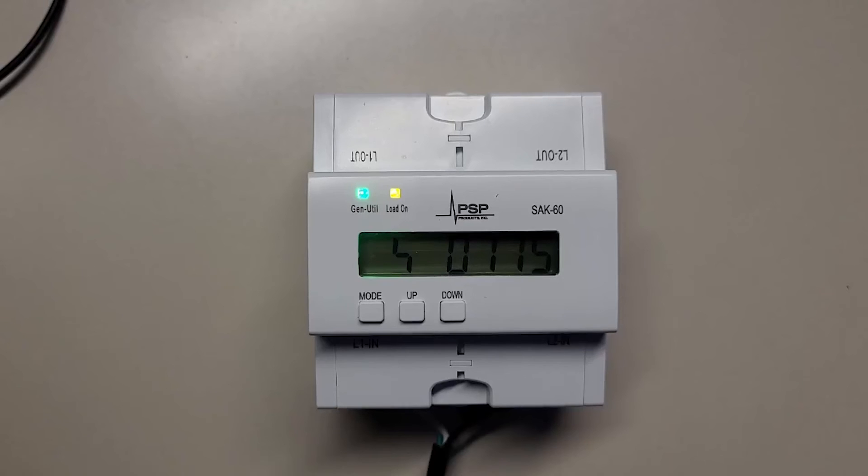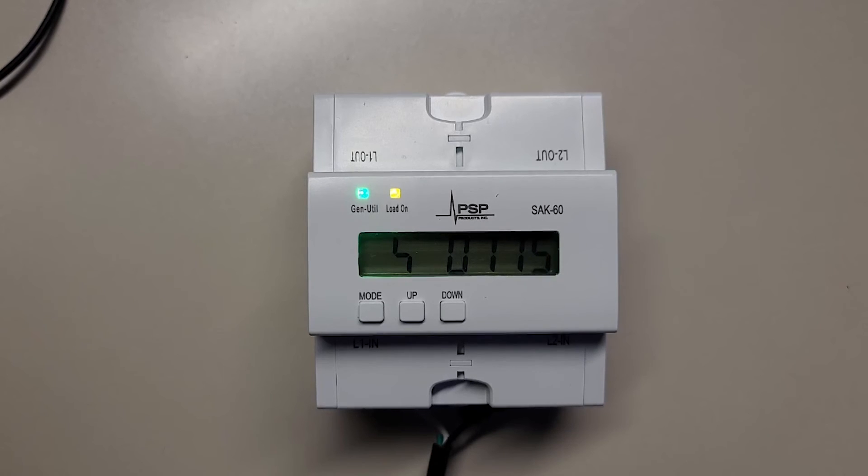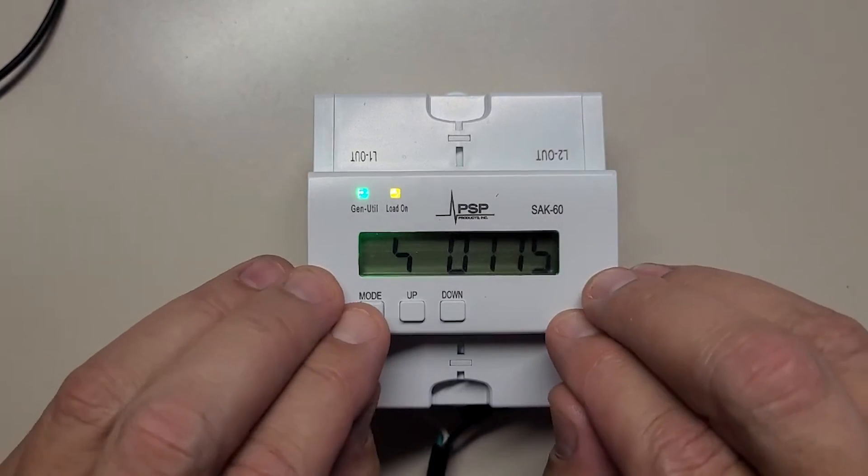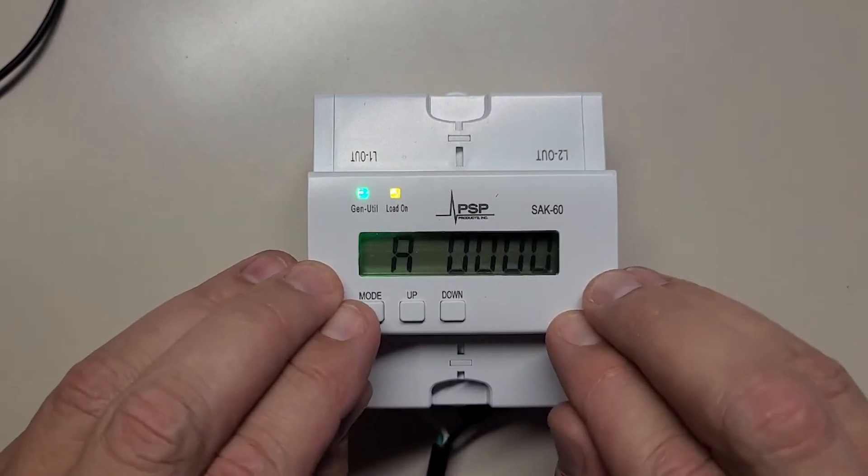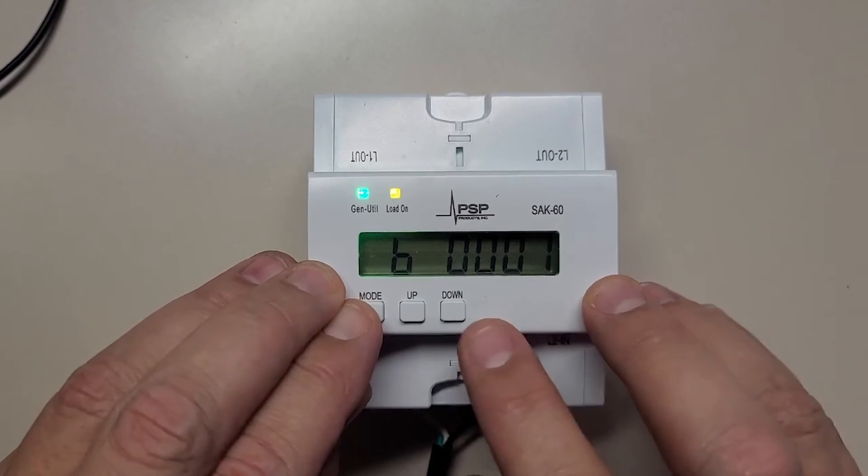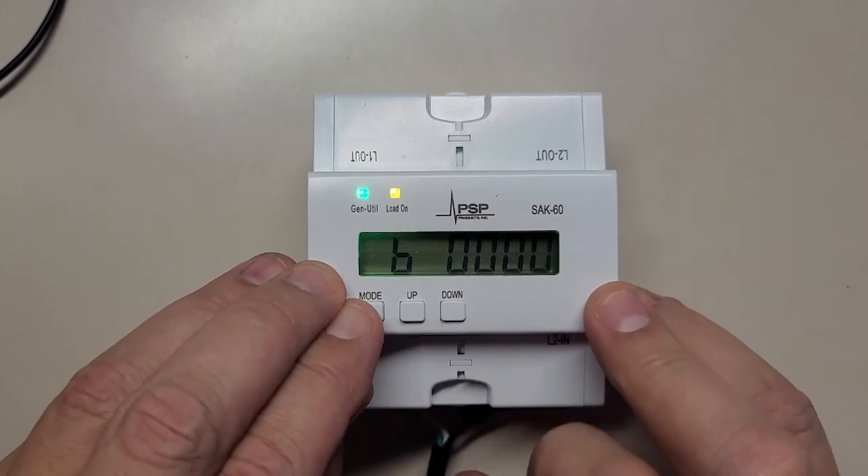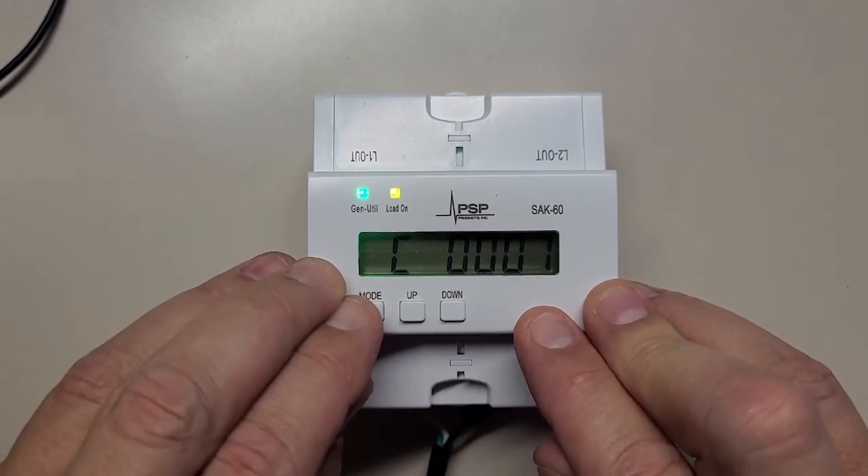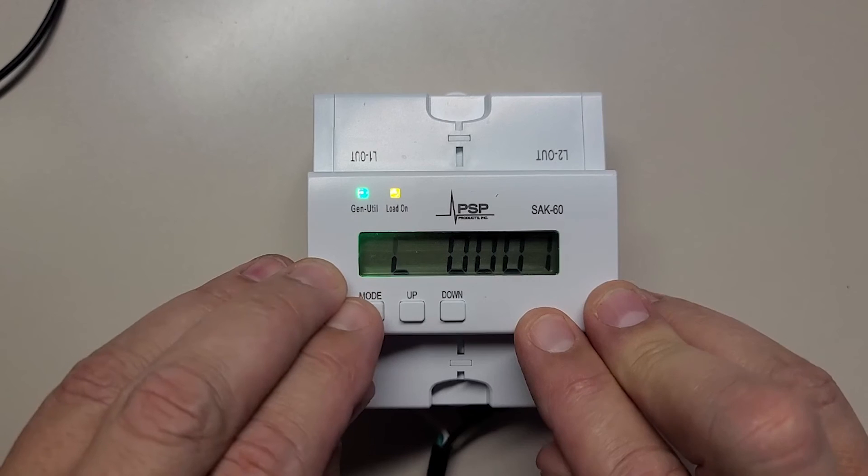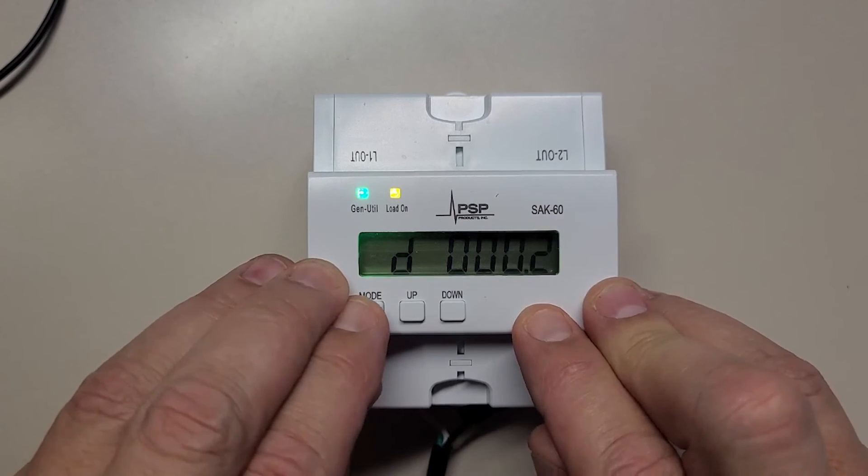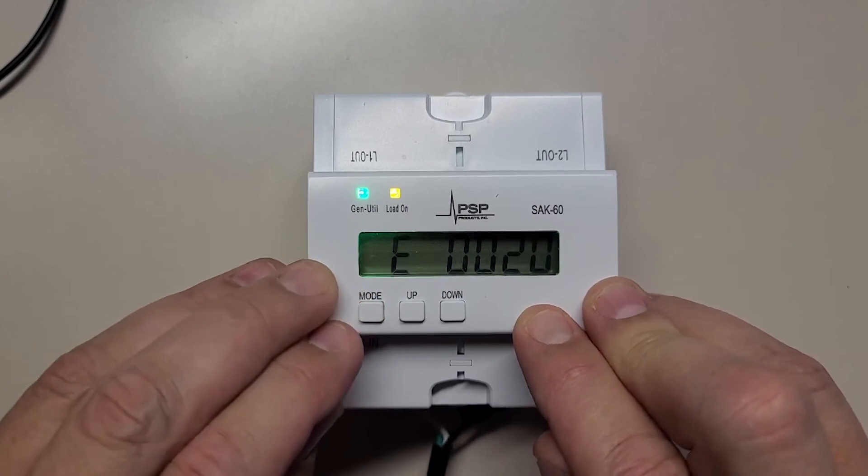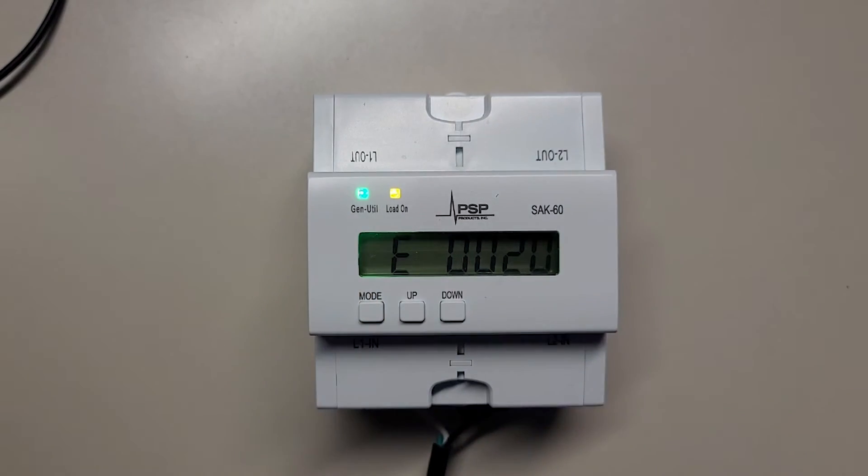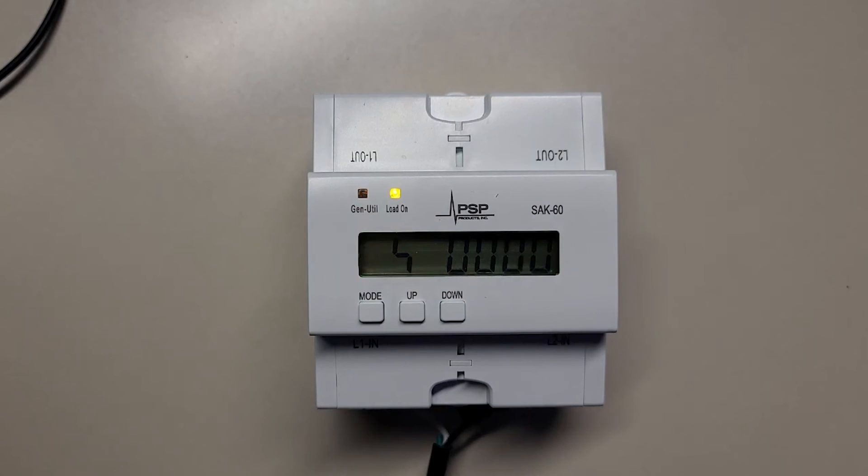As it happens, the SAK is set by default for under-frequency load management, so we will have to change menu B from one to zero. We'll press the mode button to advance. A is zero, B is one, we'll go down to zero, C is irrelevant to us, D is set to 0.2, and that's it. The rest of the menus we don't care about. We're going to allow those changes to save and the program to reload.